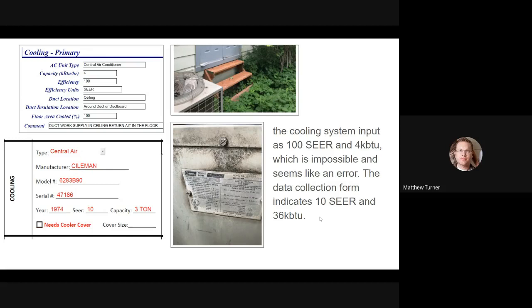The data collection form indicates a 10 SEER and 36,000 BTU. They indicated here it's a 10 SEER. Be careful, because I believe this was a MIA audit, and the way you enter data there, it shows efficiency and efficiency units, so you're identifying this as SEER, and 100 SEER isn't possible, or at least I'm not aware of any. So it's pretty obvious they accidentally added a 0 there. As for the capacity, I'm not sure where that came from. My guess is the auditor didn't understand how to identify or figure that out.